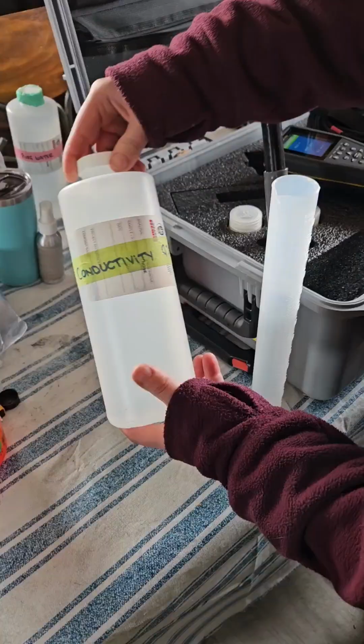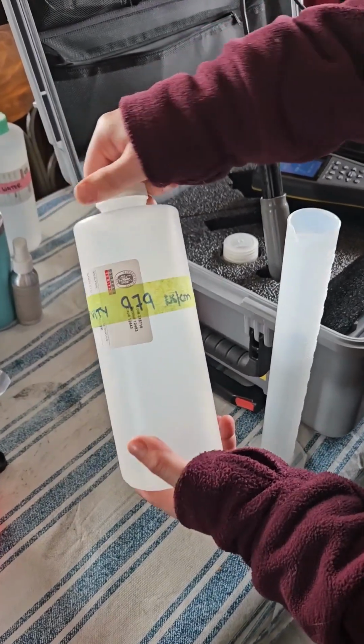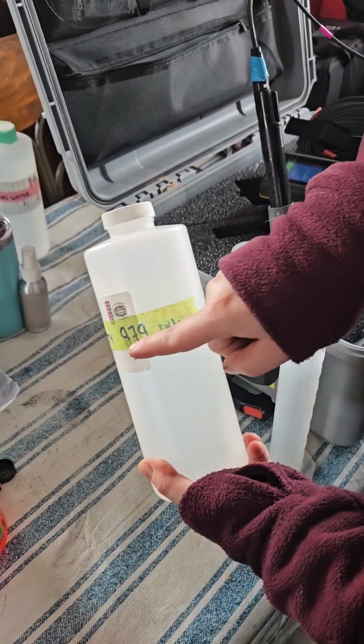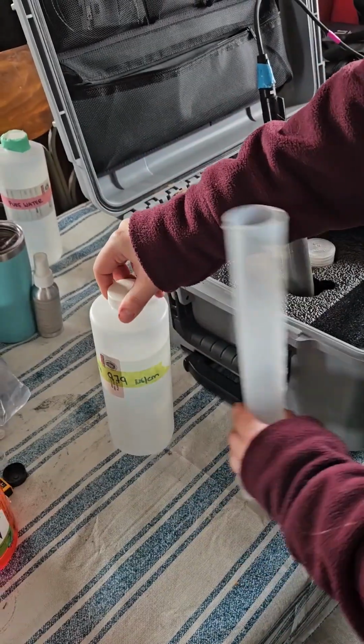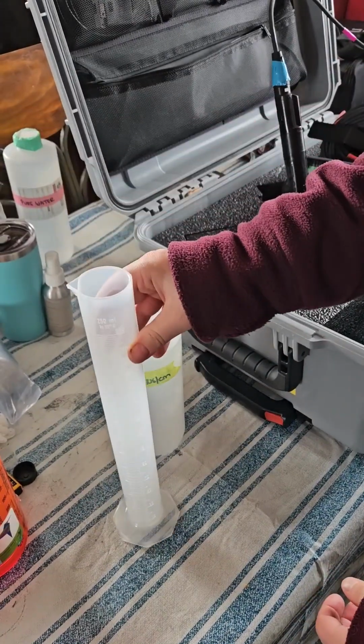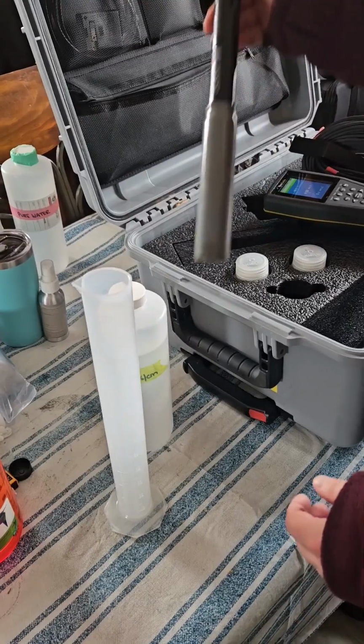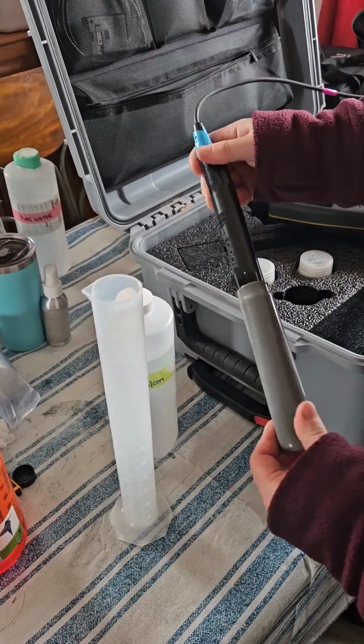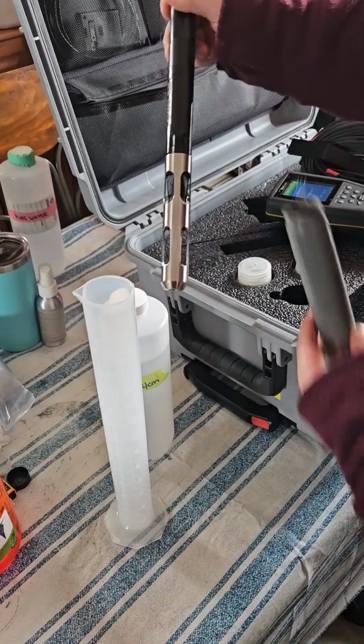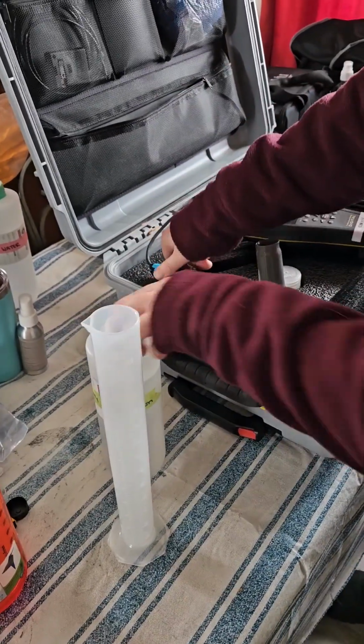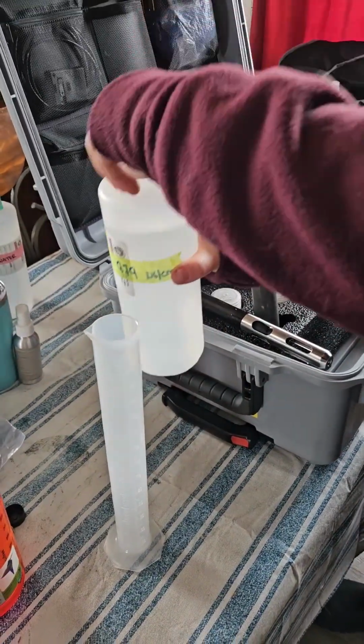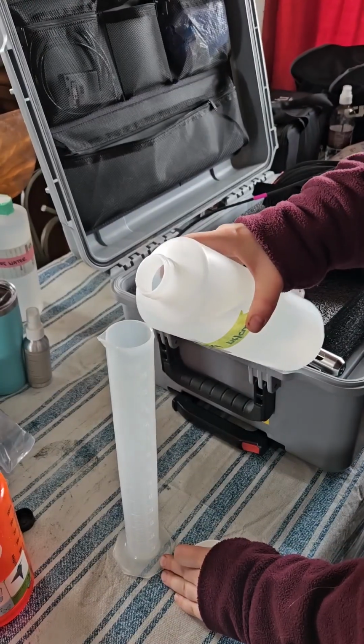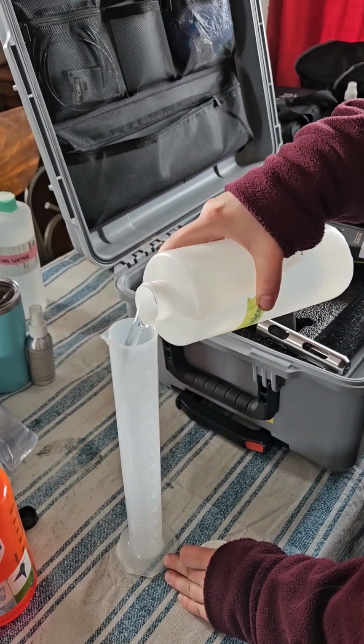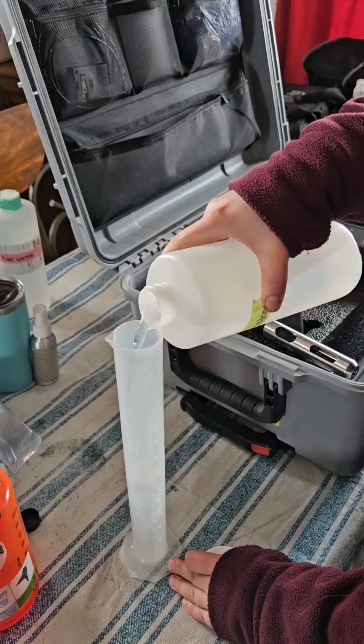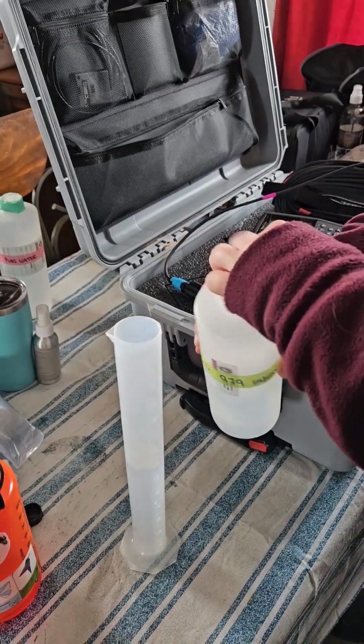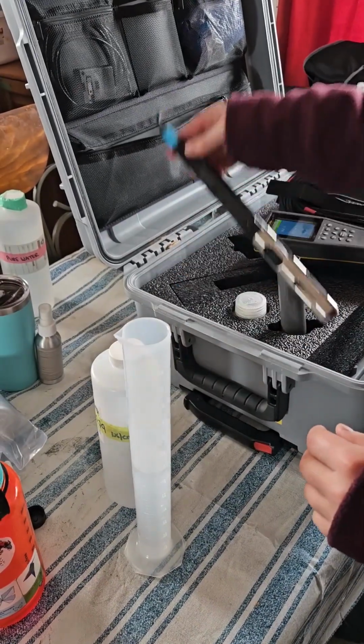So you will take your calibration solution that will be in your kit and take note of these numbers because we will use them later, and your graduated cylinder. And we will take our probe and take the gray sleeve off, leaving the metal covering on for this one. And we will fill the graduated cylinder with the calibration solution. And we want to fill it so that it's halfway full, and then we will put our probe in the cylinder.